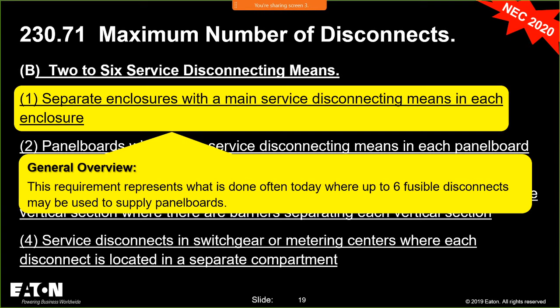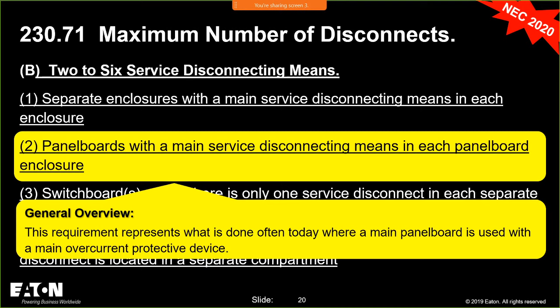Now, here is another change that says panel boards with a main service disconnecting means in each panel board enclosure. Now, that tells us that I'm not going to see a panel board anymore that has 6 overcurrent devices inside. That's gone. That's what you used to do. You're going to have to change how you do business because now you're going to need to have a main service disconnecting means, or you might go to option 1.